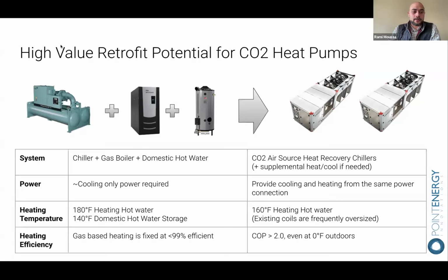Okay, so some great opportunities there. And last but not least, in cold climates, the efficiency of CO₂ as a refrigeration process is far improved. So even at 0 degrees Fahrenheit outdoors, we're still operating above a COP of 2, or twice as efficient as electric resistance. Conventional refrigerants are typically sub 2.0, maybe 1.8 or so. And so you actually see an improvement in the amount of power that would be required versus conventional refrigerant systems.